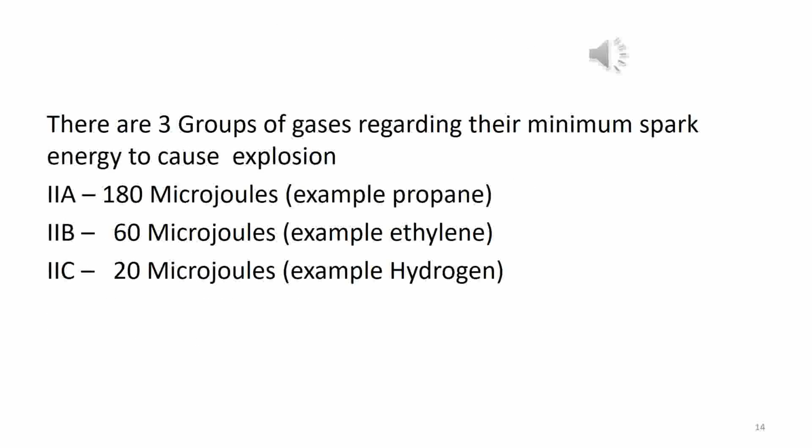There are three groups of gases regarding their minimum spark energy to cause explosion. 2A, 180 microjoules, example propane; 2B, 60 microjoules, example ethylene; 2C, 20 microjoules, example hydrogen.